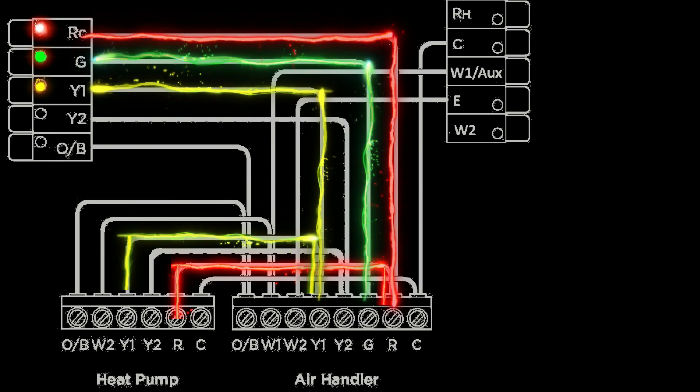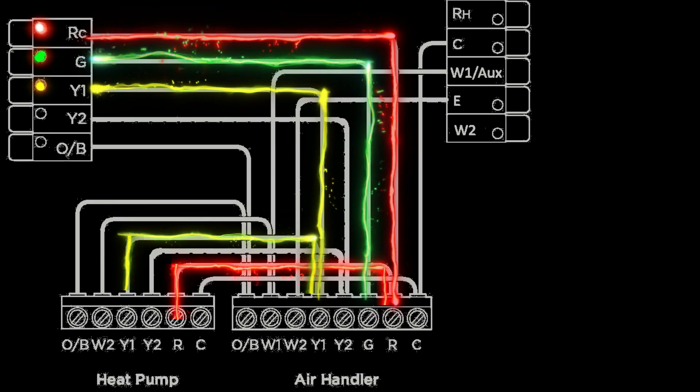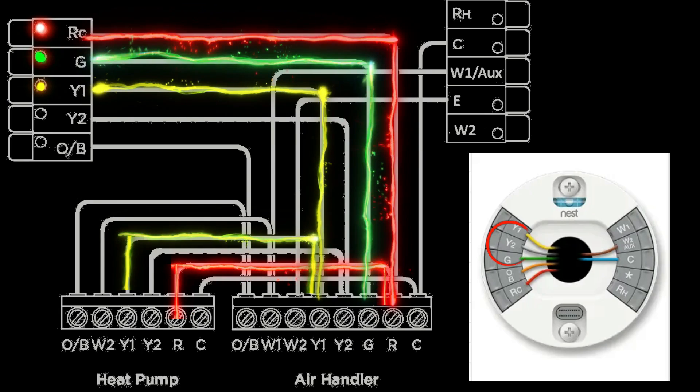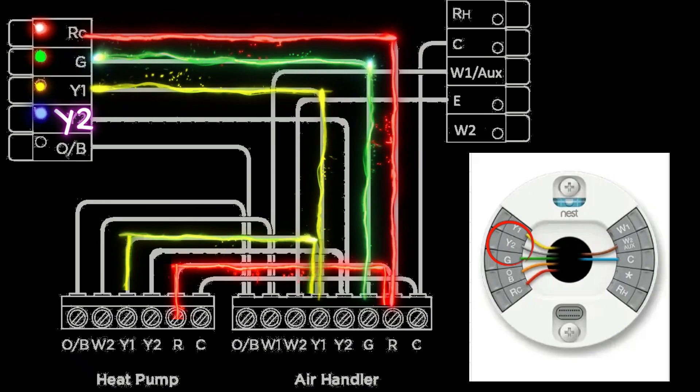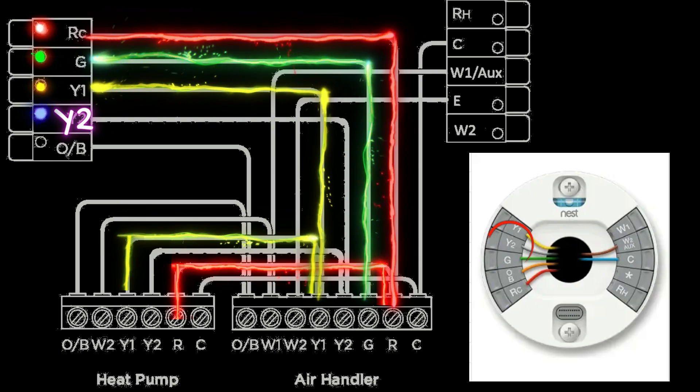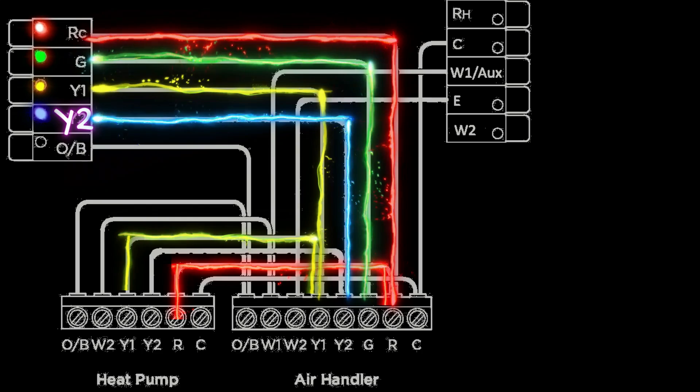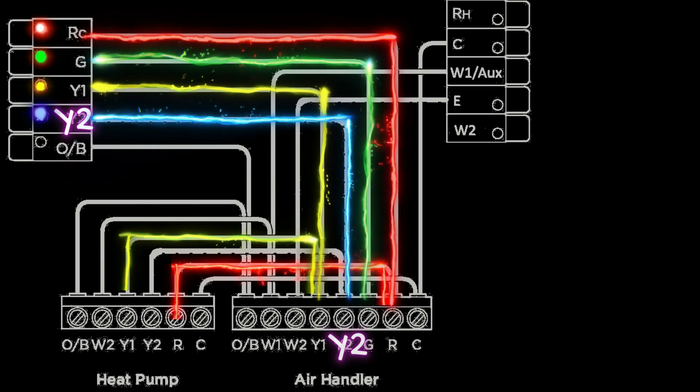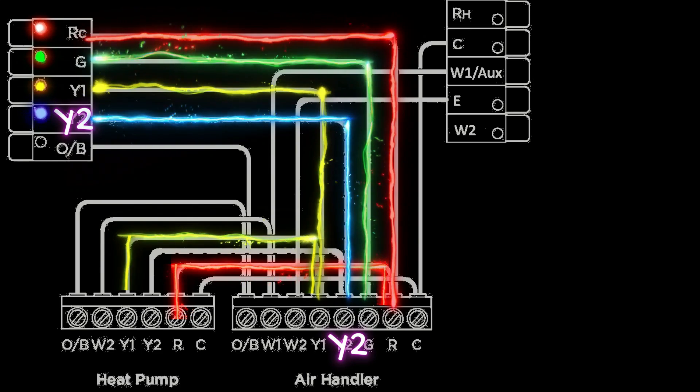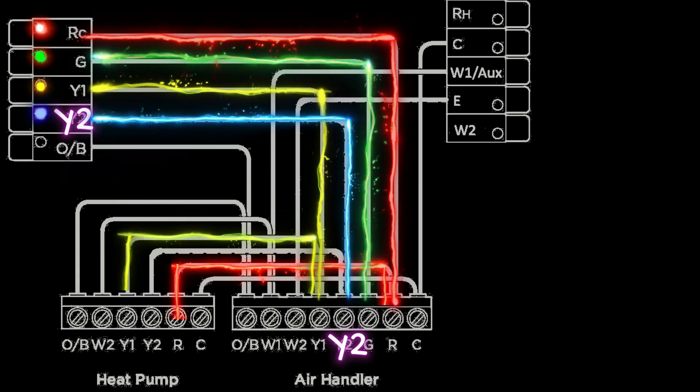Either way, when the thermostat activates second stage, it is going to activate the Y2 terminal. Now this 24 volts is going to leave the Y2 terminal on the thermostat, usually on a blue wire, and it's going to go to the Y2 terminal on the control board in the air handler.